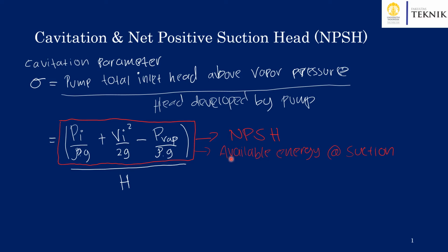Visually, we can observe cavitation by seeing bubbles surround the impeller or the eye of the impeller of a centrifugal pump. When cavitation occurs, we can hear a higher noise and it increases the vibrations of the pump and it might cause cracks on the structure of the impeller. Moreover, it will lead to a decrease in the pump efficiency.